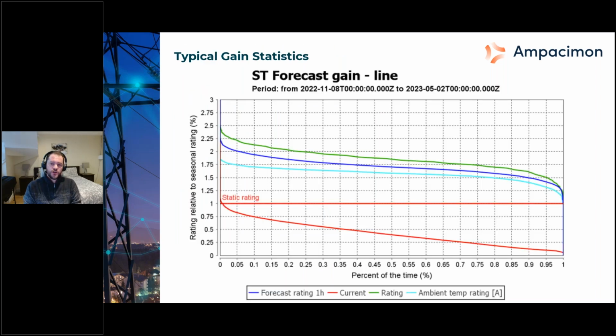So typically, when you look at DLR or AAR or any sort of rating, you're moving from something that is a static rating for all time, and you're moving that to a statistical rating. So it's a rating that depends on whether the weather is conducive to that. If you look at this chart here, it's showing percentage of time on the x-axis versus the relative rating on the y-axis. I've said that it's percentage, but in reality it is per unit.